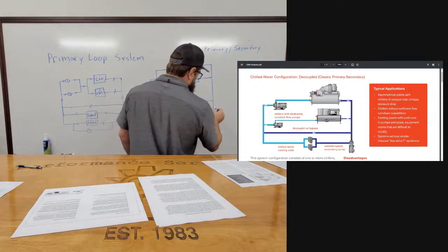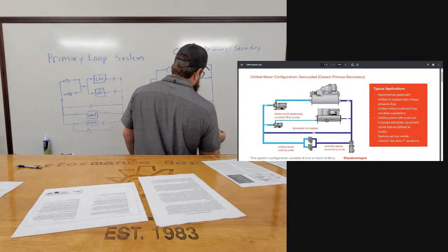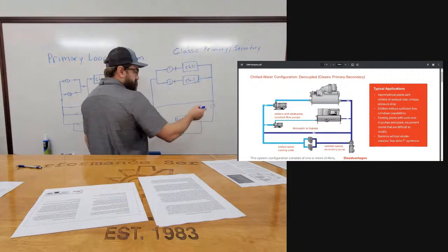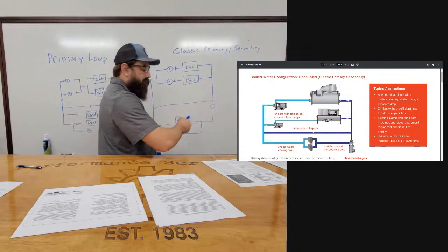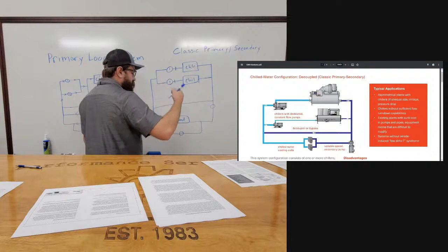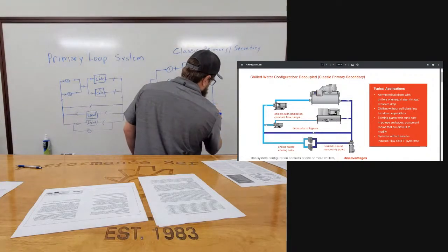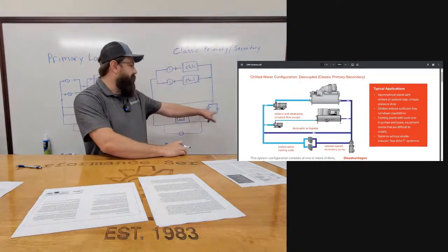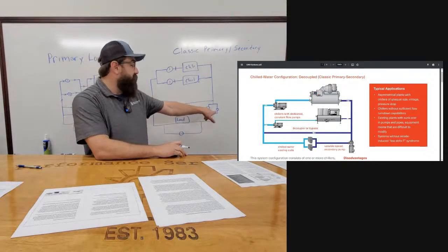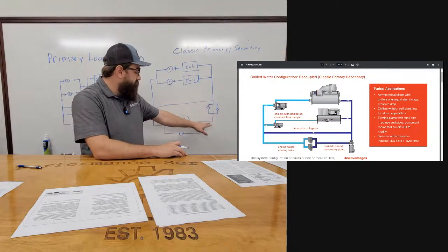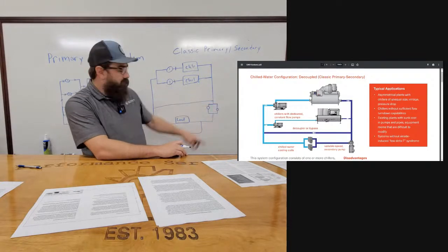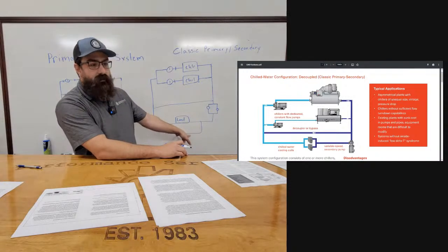let's see, I guess you'd have a pump. Comes out the primary. Yeah, here. Right, pumps? Yeah. On the pushing water through your loop, not pulling. So you would have, actually, let's do it this way. That's how most of ours are. We would have two pumps on the primary, which can lead lag. Those pumps would be on a VFD that maintain pressure through the building. And then you have a bypass valve that can also open and close.